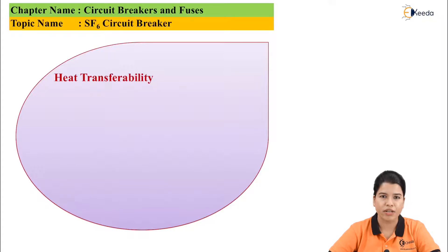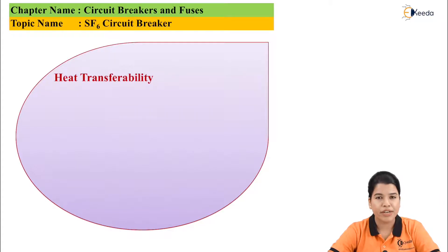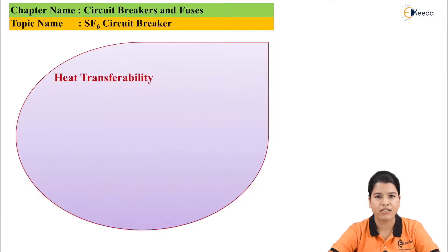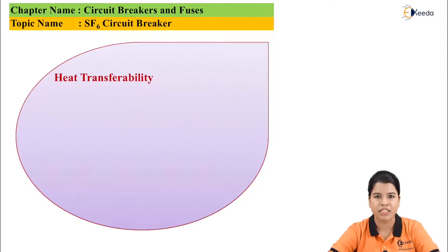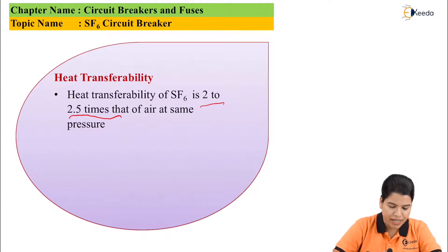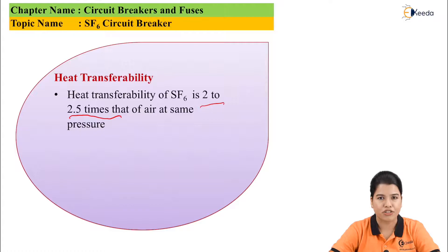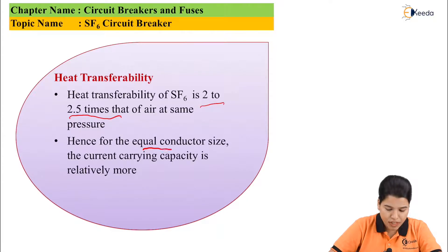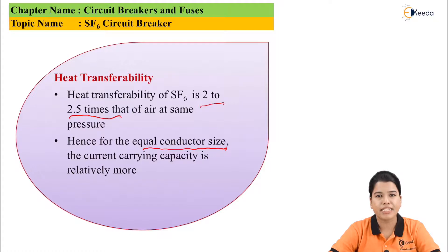The next property is heat transferability, which is very important in the arc quenching process. When the contacts are separated and an arc is struck between them due to heavy current, the temperature increases. One method of eliminating the arc is by cooling it. If the arc quenching medium has a high value of heat transferability, it is better. The heat transferability of SF6 gas is about 2 to 2.5 times that of air at the same temperature and pressure, so for equal conductor size the current carrying capacity is relatively high.